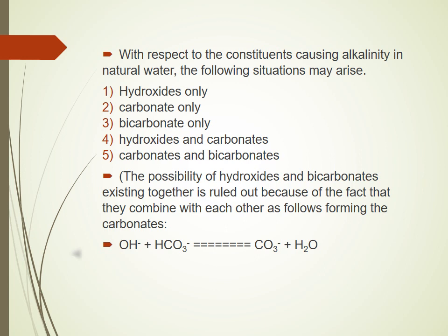Now, the important thing is that highly alkaline water causes caustic embrittlement. So what is caustic embrittlement? It is the phenomenon during which the boiler material, or any metal, becomes brittle due to the accumulation of caustic substances, and that's why it is one of the fast types of boiler corrosion, caused by the highly alkaline condition of the water.